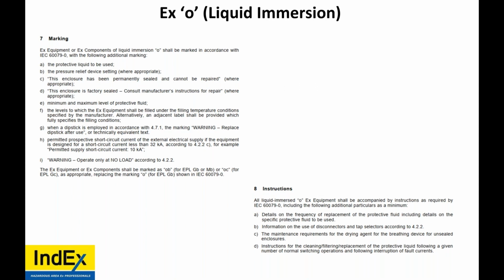Now, for Ex o liquid immersion, what about marking? Well, there's a lot of marking requirements as well. It has to be marked with what protective liquid is used, which pressure relief device is used and its setting. It shall indicate if it's permanently sealed, or if it's factory sealed, meaning that it can be opened, but it has to be opened and closed as per the IOMs. It has to be repaired, as they say. Now, the levels of EX protection followed, so Ex ob or oc, shall be on the EX data plate. Mentions of dipsticks, mention of short circuit capacities, and warning labels.